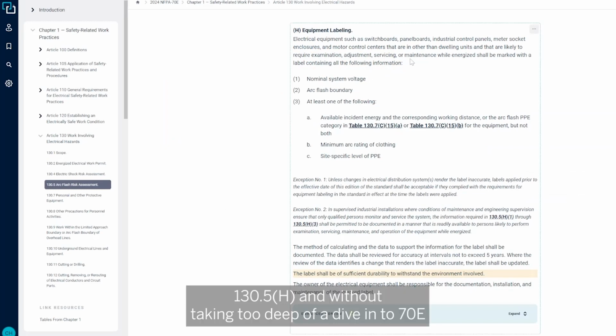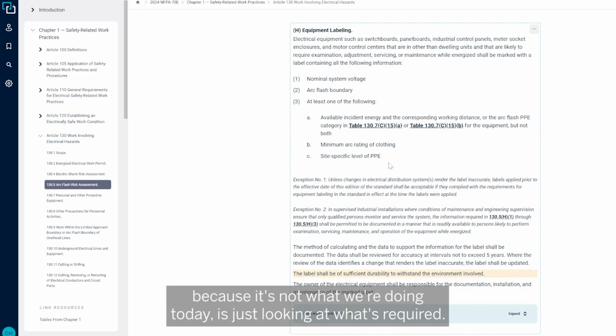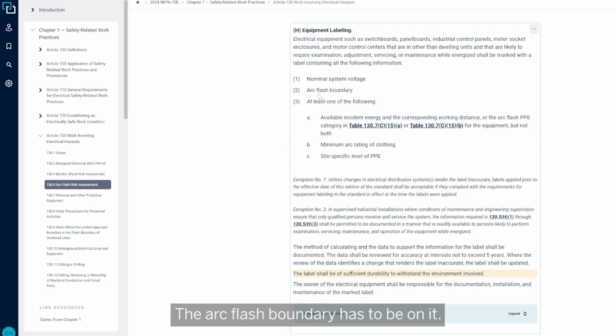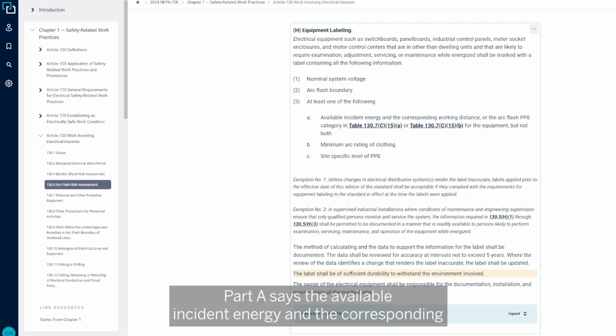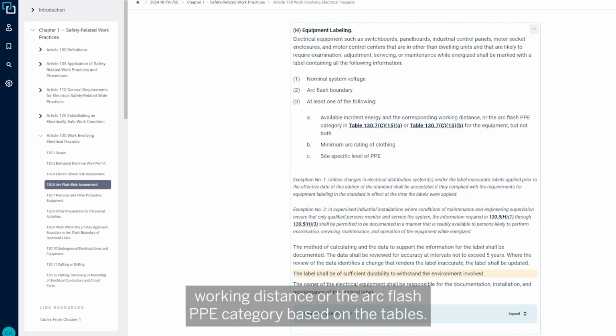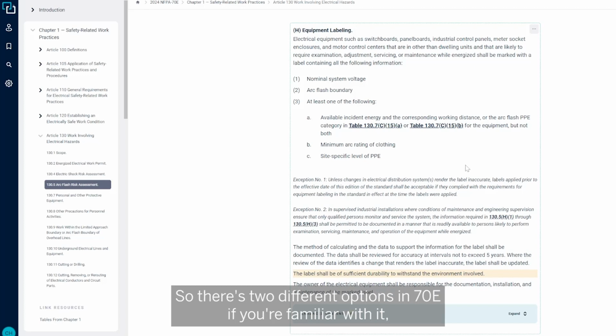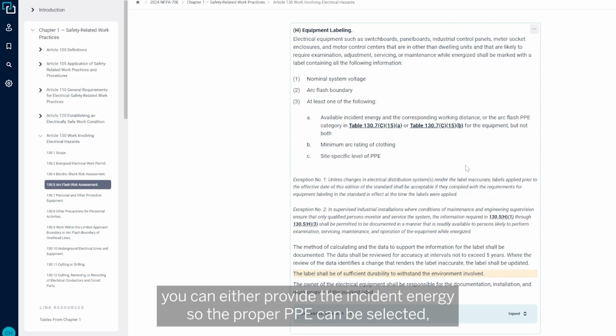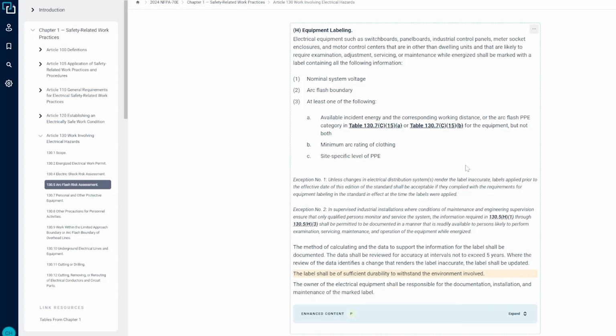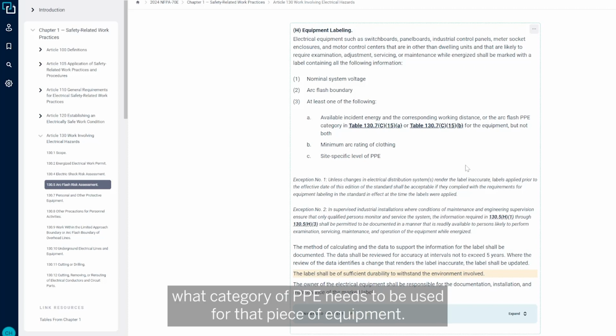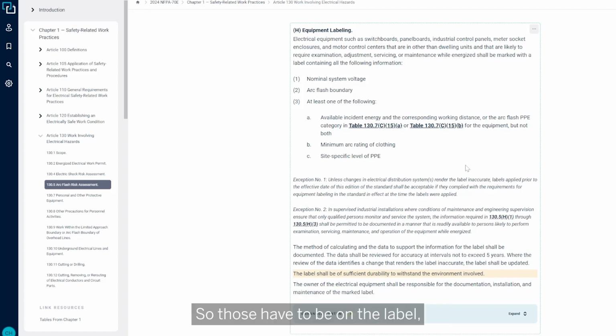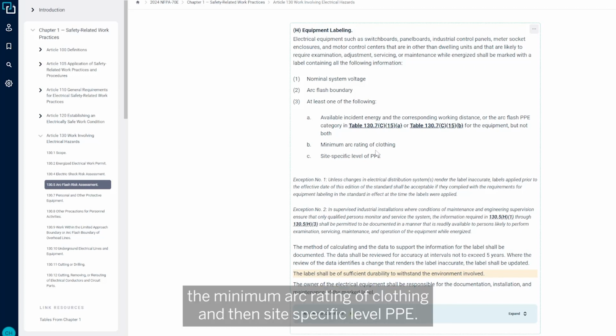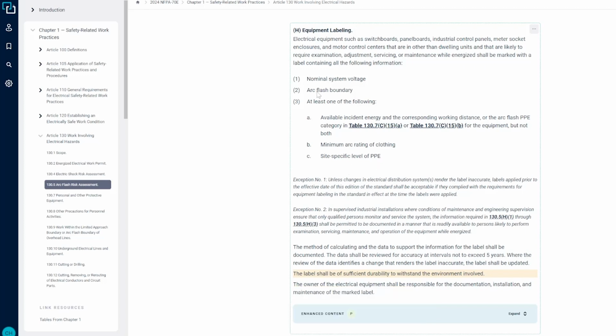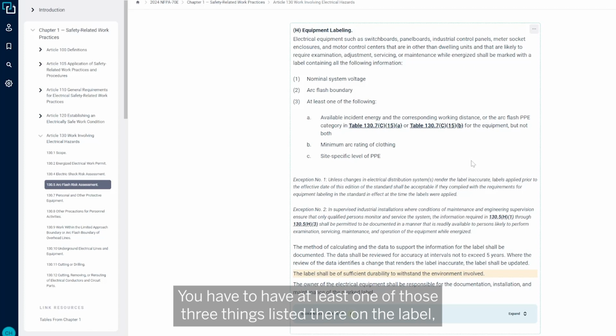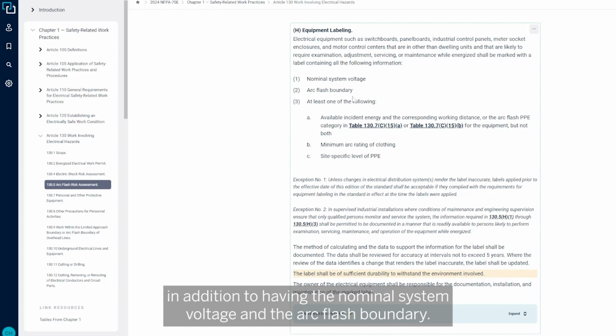I'm in 130.5(H). And without taking too deep of a dive into 70E here, because it's not what we're doing today, is just looking at what's required. So we have nominal system voltage has to be on it. The arc flash boundary has to be on it, so that'll have to be calculated. And then at least one of the following. Part A says the available incident energy and the corresponding working distance, or the arc flash PPE category, based on the tables. So there's 2 different options in 70E. If you're familiar with it, you can either provide the incident energy, so the proper PPE can be selected, or you can use the category method, which will tell you what category of PPE needs to be used for that piece of equipment. So those have to be on the label, the minimum arc rating of clothing, and then site-specific level PPE. You have to have at least one of those 3 things listed there on the label, in addition to having the nominal system voltage and the arc flash boundary.